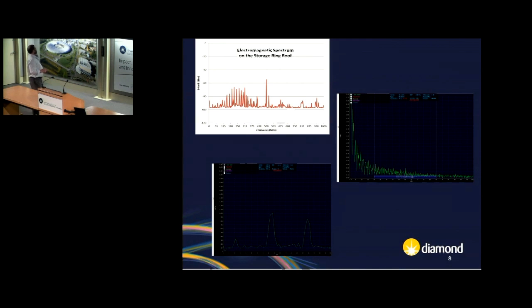Just for completeness, on the bottom left hand, these two spikes here are at 100 and 150 hertz, second and third harmonic of the supply frequency. The interesting thing about this slide is we don't get 50 hertz, which means we've managed to balance the loads across the supply quite well. So all in all, we've done reasonably well at keeping the noise down in Diamond. So that's it.